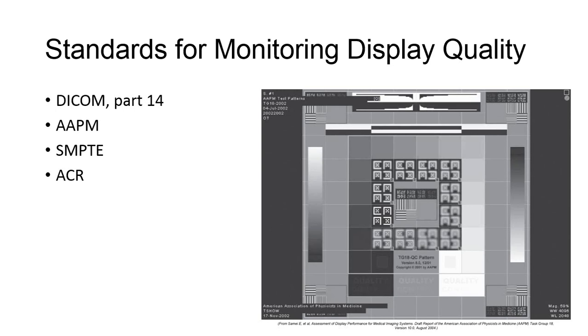Several scientific groups have published guidelines for monitoring the quality of electronic image display devices. DICOM, specifically Part 14, provides standards for medical images. Other tests and guidelines are available from the American Association of Physicists in Medicine, AAPM, the Society of Motion Picture and Television Engineers, SMPTE, the American College of Radiology, ACR, among a few others.